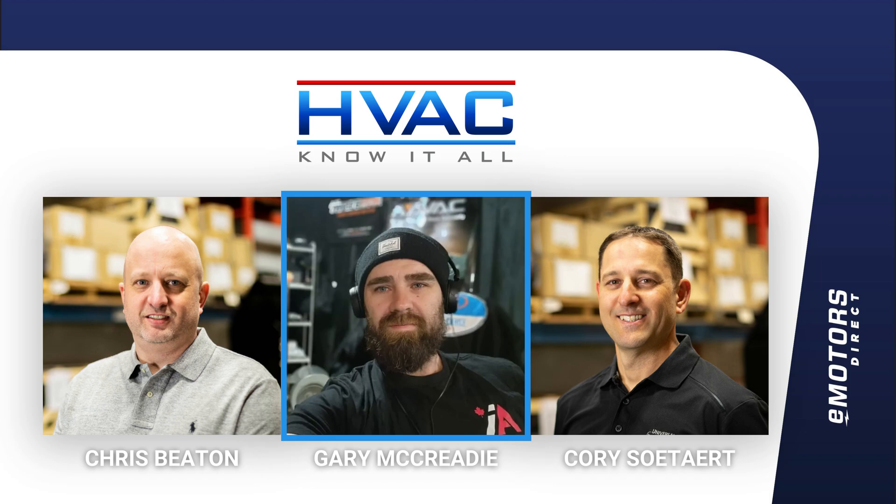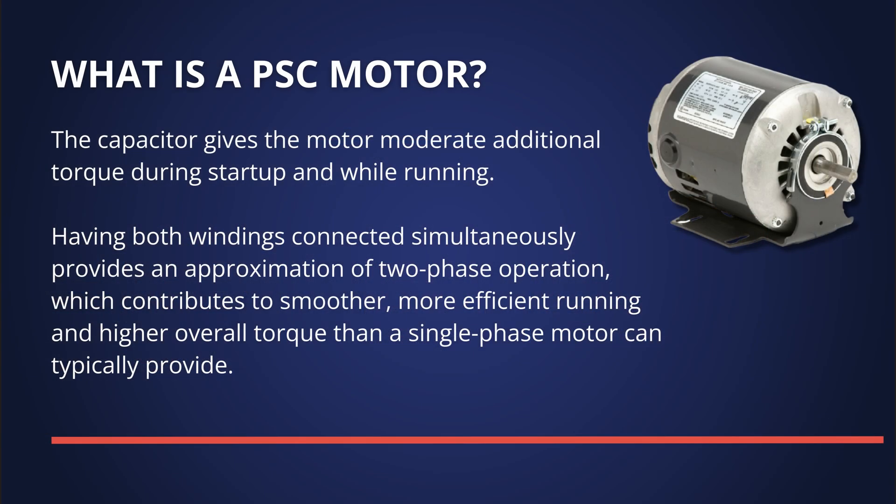Blower motors, not so much — most of them are three-phase in the commercial work I do. But going back to the technical side: reading in this article, both windings are engaged at all times. There's no way to take that start winding out of the motor once it gets up to speed. On a permanent split capacitor motor, there is a main winding, an auxiliary winding, and a run capacitor. The auxiliary winding and run capacitor act as your start circuit — telling the motor which direction to run and providing starting torque — but they do stay in the circuit all the time.